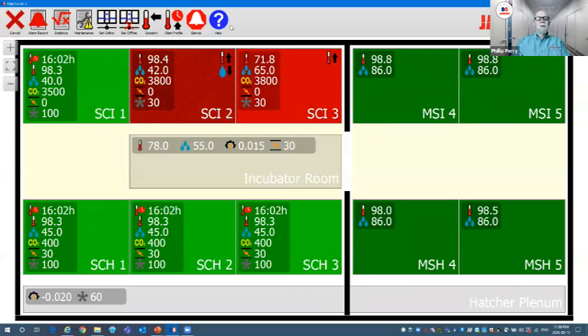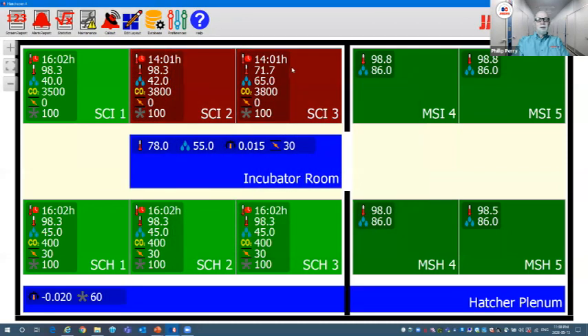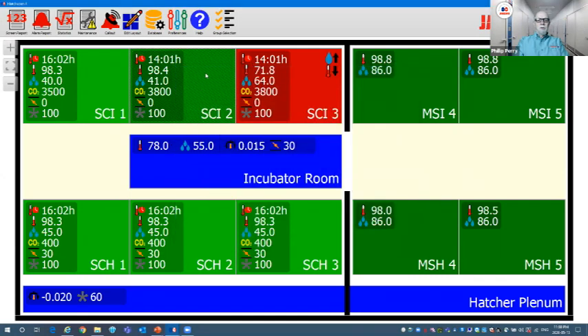I'm going to do the group. We're going to start our profile. Let's say we had them on the 29th, just to get our dates similar. So this machine right now, the maroon one, was in alarm. We can see that it had a high temp and low humidity, grayed out. We can silence that, take those off, and the machine turns to normal.